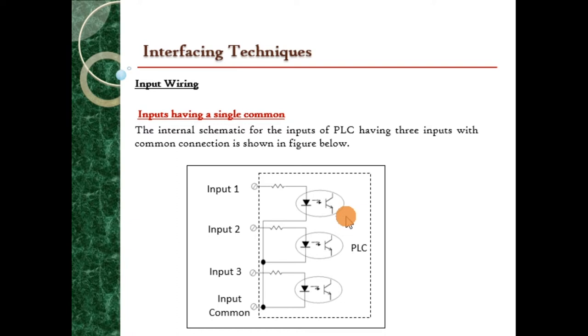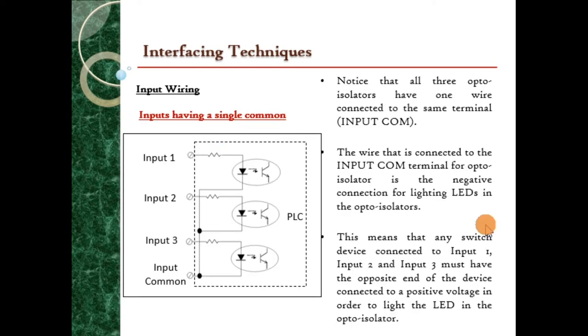We start with the first input wiring, having a single common. In this wiring, the schematic shows that all the inputs to the PLC have a common connection. You can see here that the negative line of each circuit is connected to one common, meaning all of these inputs to the PLC share a common connection. It can be a ground, for example. The wire connected to the input COM, the input common terminal for the opto-isolator, is the negative connection for lighting the LEDs in the opto-isolator.